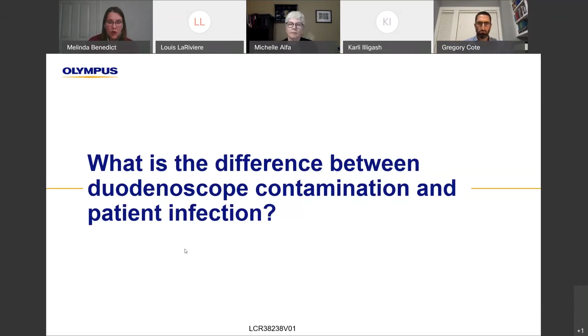The sources of endoscope contamination, and when I talk about endoscope contamination, I'm talking more about when you do culture and they identify that the scope has been fully reprocessed, but it has some contamination that's detected on culture. And so to me, the sources of that can be failure of the reprocessing, where for some reason the cleaning and the high level disinfection or sterilization didn't work, and that scope has organisms in it that actually weren't properly eradicated from patient use. So that's one source. That's a dramatic one. We hope that happens on very rare occasions. And I know that as more facilities look at their endoscopes, they will find that contamination shouldn't be affecting 80% of your scopes that are being used in any way, shape, or form. In fact, it should actually be extremely low. So one source would be failure of the actual reprocessing.